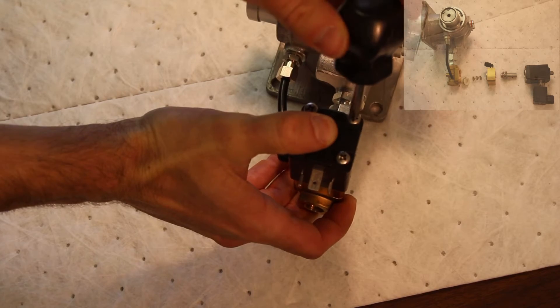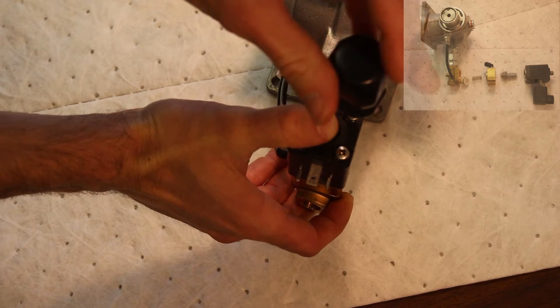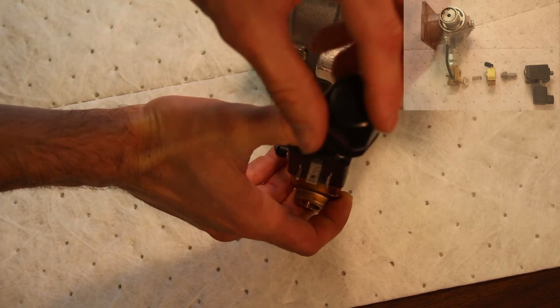Tighten the four bolts that hold the valve together. A moderate amount of tension will do. Too much may strip the threads from the brass housing.